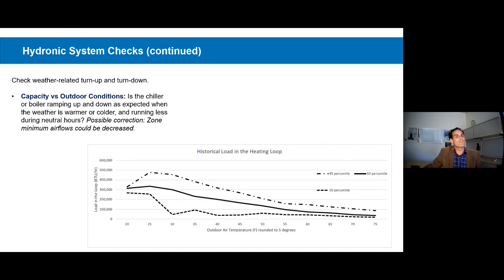And in the case of boiler systems, I have to point out how big the variance is between traditional calculation methods and reality. On this project, the design engineer did a load calculation in the classic manner, envelope and then outside air, and they came up with 2.5 million BTU. And you can see the maximum load that we've ever incurred in this system is 500,000 BTU. So that classic load calculation is off by a big factor, a factor of 5, right?